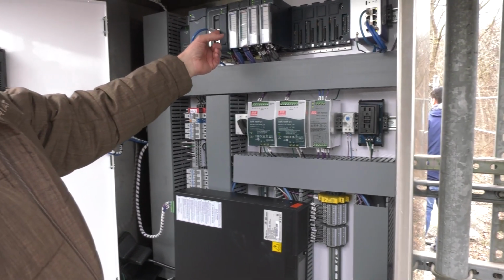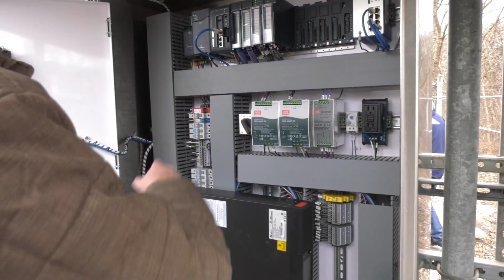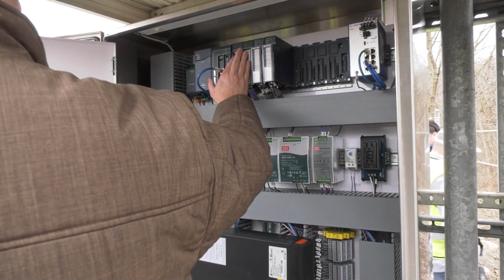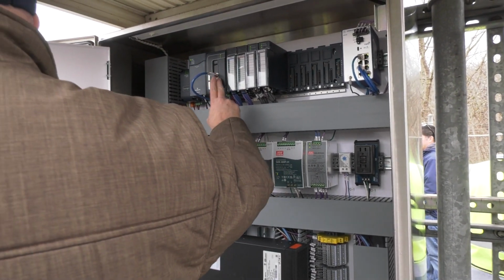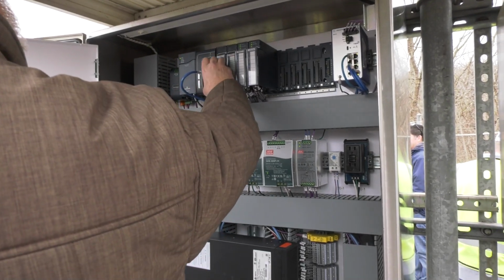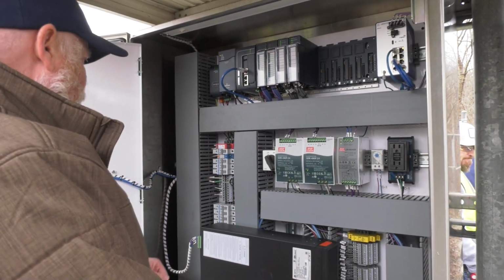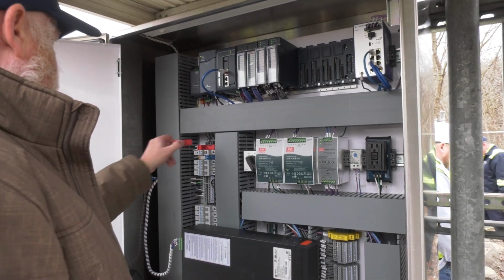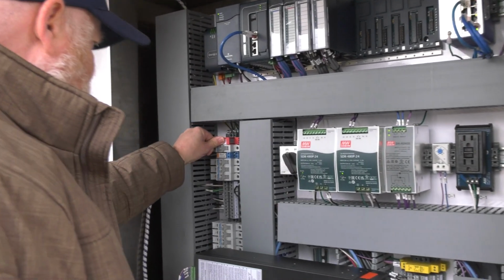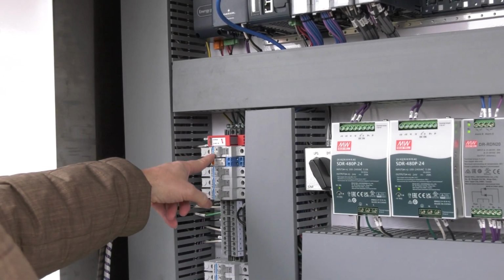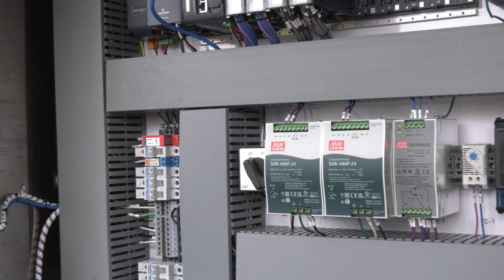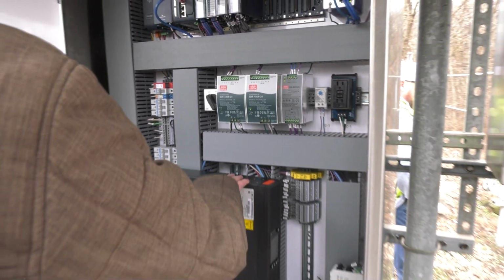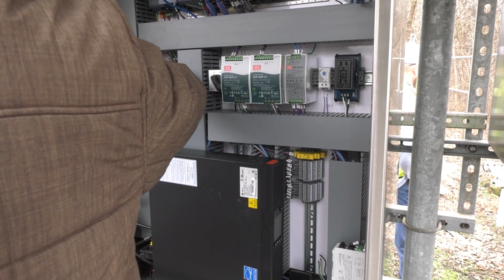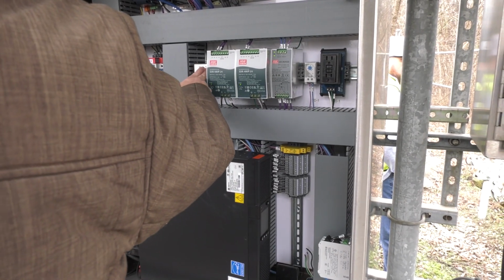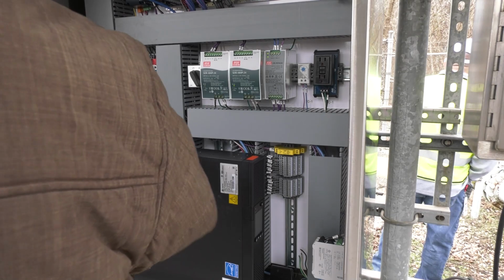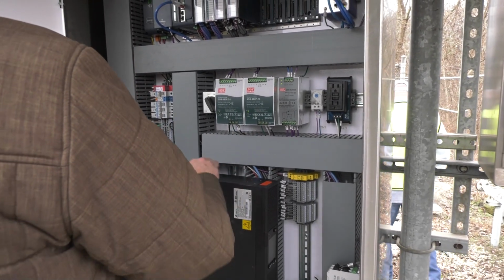And the PLC, again, the switch, very important. You'll probably never see it not on, but in case maintenance happens to replace one of these and they don't know to flip it over, it's good to know about. And again, the surge suppressor, that one is make-before-break. This is your main circuit breaker. If you have to kill power to it, just flip that and it'll kill the power. You will maintain power off the UPS. So if you kill this, just leave it, put it in bypass, and that'll bypass your 120 off of your UPS. And again, your circuit breakers.